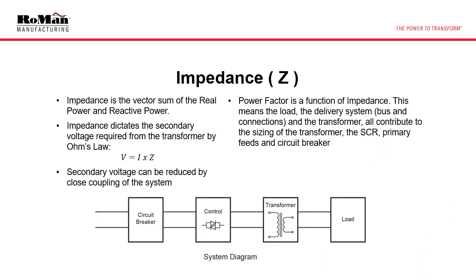In summary, impedance can be thought of as the overall AC resistance of a system. Ohm's law tells us that if we can reduce overall impedance of the system, we will need less voltage to drive the same amount of current. This means smaller, less expensive transformers and less power usage. Additionally, the angle formed in the impedance triangle is the same angle in the power triangle, which is the displacement power factor. Lower displacement power factor means higher penalty from the power company.